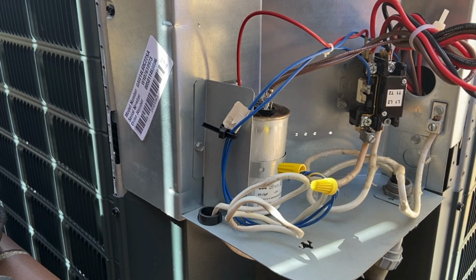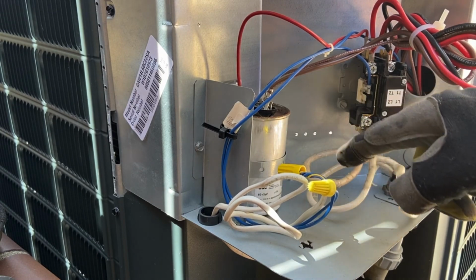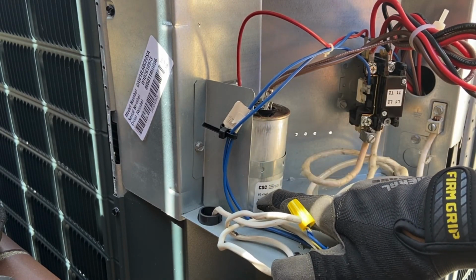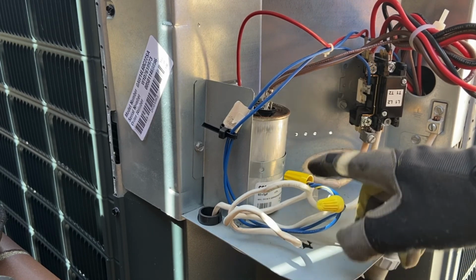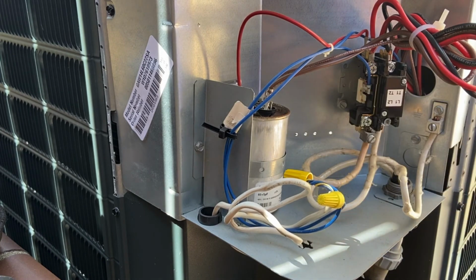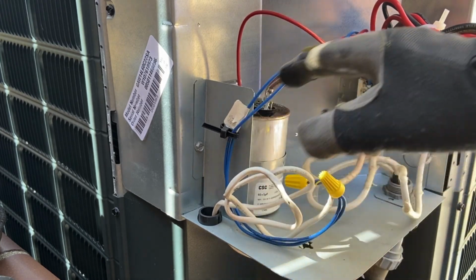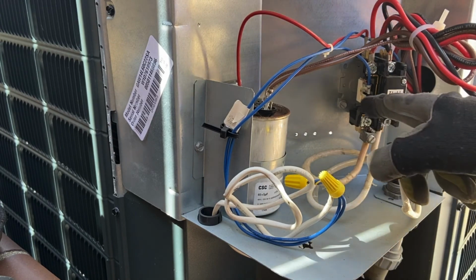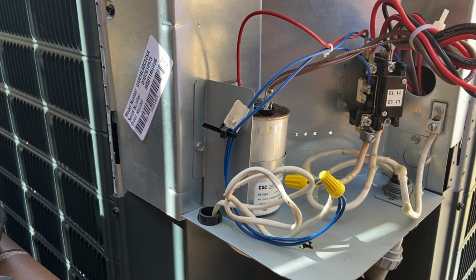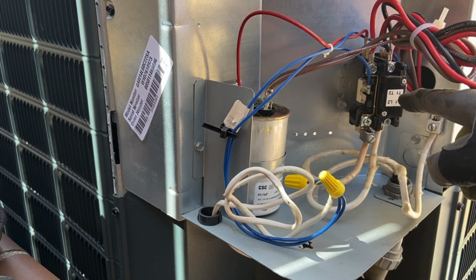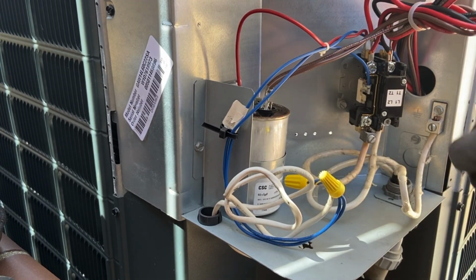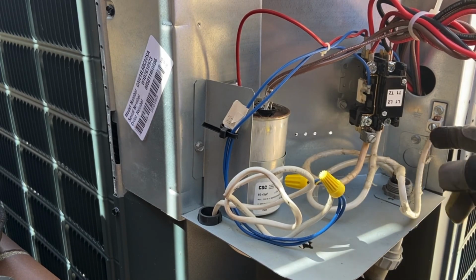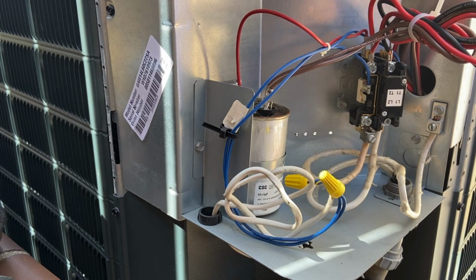Okay, up in the control panel side, I've got my dual capacitor. Looking at the specs on the side, it looks like a 60 microfarad for my compressor and 5 microfarad for my condenser fan motor, making it a dual capacitor. My low voltage control wires are coming in, two blue wires going right to my contactor. I don't have any safety controls in this unit, so they just go directly to my contactor and energize the coil on my contactor on a call for cooling from my thermostat. My L1 and L2 are coming into my contactor, and my ground wire goes over to my ground connection, connected to the chassis on the unit.